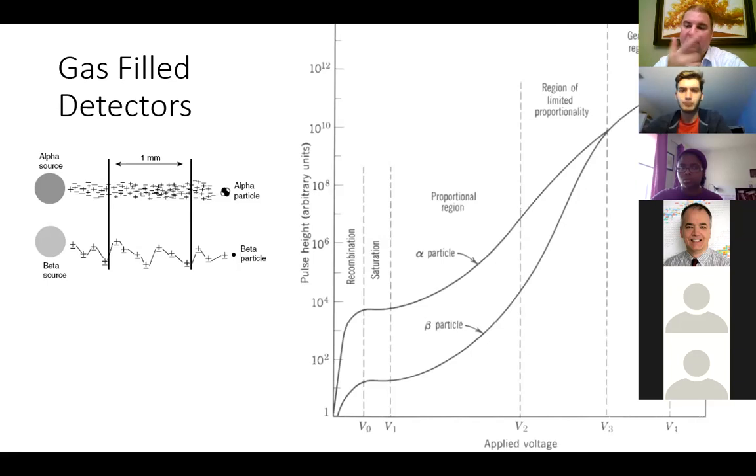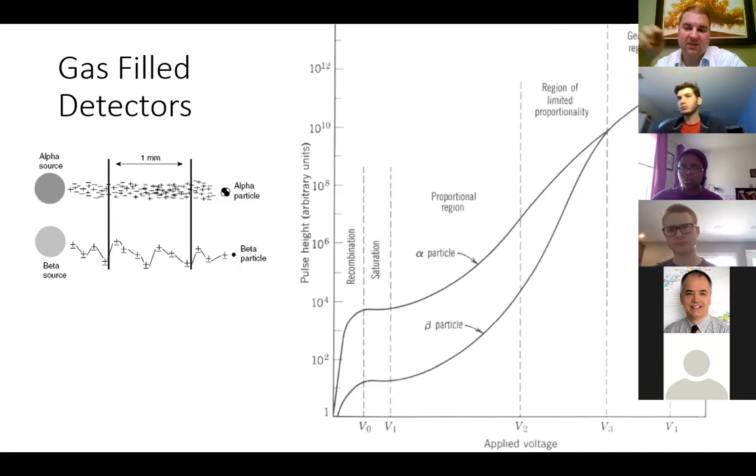It could undergo the photoelectric effect and scatter an electron, in air quotes, because you're kicking one out from an atom. And those scattered electrons would act just like a beta particle. If they get created within the detector, then those are the particles that are going to create ion pairs as they lose their energy. So it doesn't matter what is coming in, as long as you can create some sort of a charged particle in the detector itself, you can detect the radiation, okay? So these ion pairs get collected.